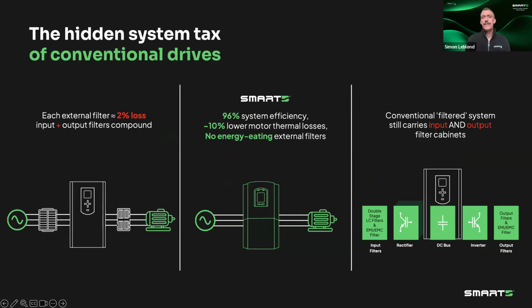You're also getting an efficiency boost. Not to say that you're competing with the affinity law, that remains your main efficiency driver. But as you remove those harmonic impacts, both on the grid and the motor side, you're removing that harmonic tax, if you want. And that harmonic tax is quite visible. If you put a filter to remove the harmonics, then it's the filter that captures that lost efficiency. But even if you don't have that filter, then it becomes the transformer, or it becomes the motor that needs to dissipate that harmonic content, and that becomes your efficiency drain. So really, with SmartD, the drive becomes the system, and you get your efficiency right up front with no hidden losses.